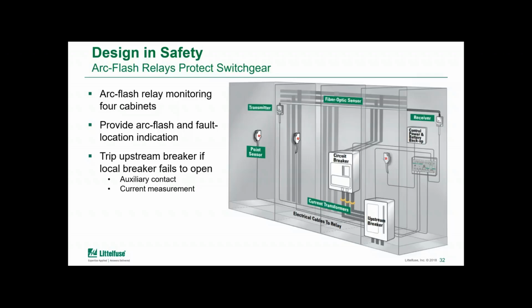And this system will then work in conjunction with the circuit breaker to protect the equipment. So the relay will provide the arc flash protection and fault location, and then the breaker will provide the clearing. Now, upon reacting to the arc flash, there is a potential that the upstream breaker might need to be connected to the arc flash relay, as the local breaker, the circuit breaker shown there, is also perhaps a device that could be subject to an arc flash. So with those 2 circuit breakers connected to the relay, you can now have a system that has enough intelligence to trip an upstream breaker if the local breaker had a fault and did not operate.